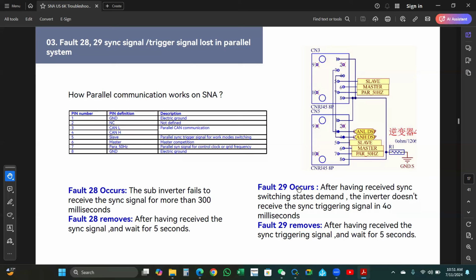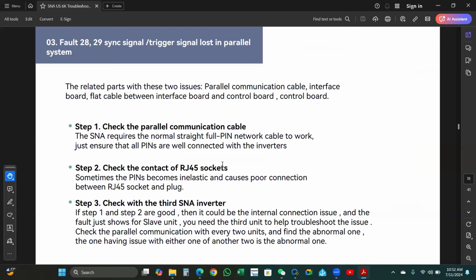Fault 29 occurs after receiving a sync switching state demand, when the inverter doesn't receive the sync trigger signal within 40 milliseconds. Fault 29 is removed after receiving the sync triggering signal and waiting for 5 seconds. The related parts for these two issues are the parallel communication cable, the interface board, the flat cable between the interface board and the control board, and also the control board.